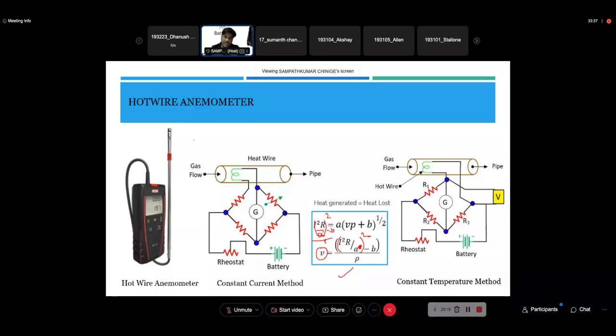But what we have here is a single one-dimensional flow, one-dimensional hot wire anemometer. So it will give the values directly over here. Okay, it's not a 2-wire or 3-wire hot wire anemometer. So we are not following this. Directly the digital values will come over here.